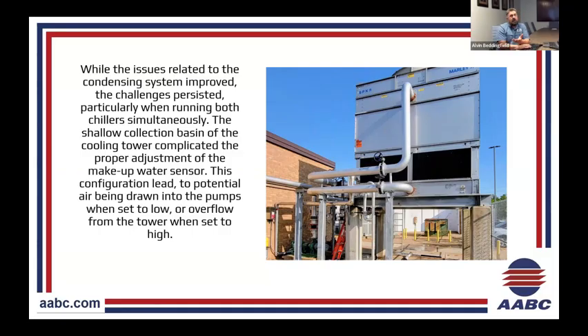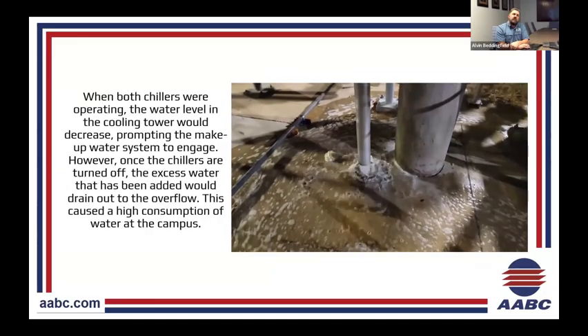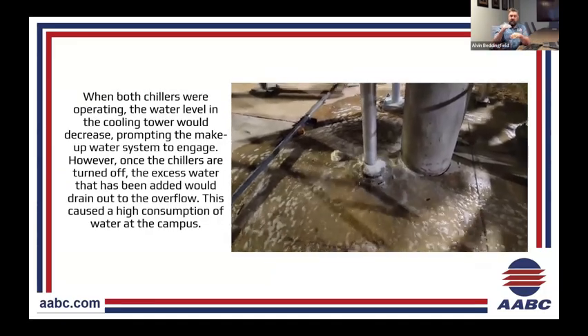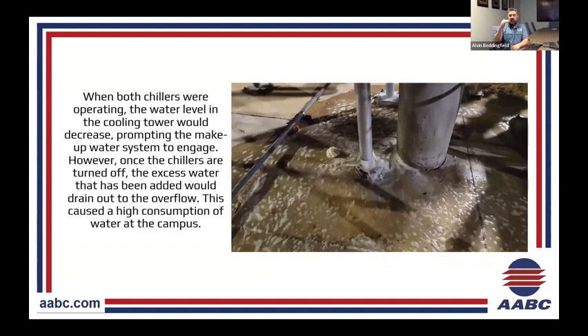This was to try to avoid the cavitation that the pumps are experiencing. And as I said, one tower would run fine, either the larger tower or the smaller one, or the smaller chiller, the larger chiller. But when both ran, we'd still slightly pull air into the system eventually. So what would happen was, once you fill that overflow up too high, the tower pump would rise and the water levels would drop once the tower turned on.